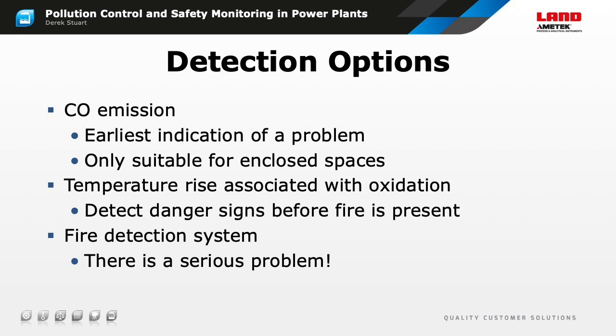We have three ways to detect spontaneous heating. Our aim is to detect the danger signs before a fire is present. Carbon monoxide emissions give the earliest indication of a problem, but they can only be used in enclosed spaces. This is because wind will quickly disperse any emissions before a measurable concentration can accumulate in an open area such as a storage pile. That makes CO detection ideal for use in silos, storage domes, and pulverizers.